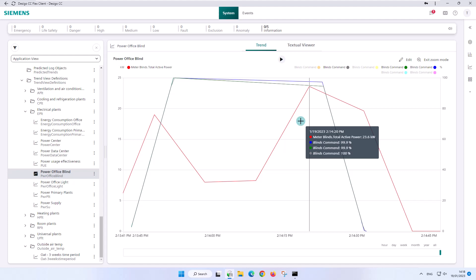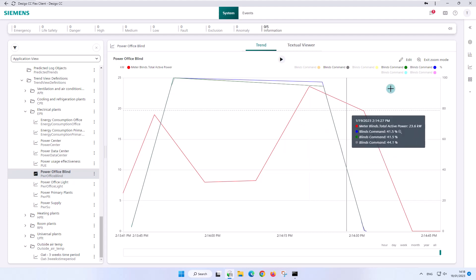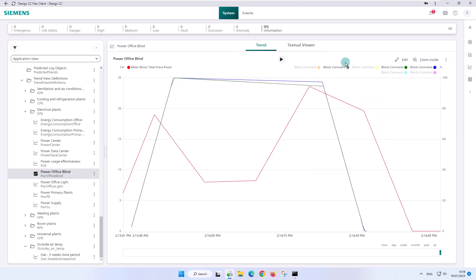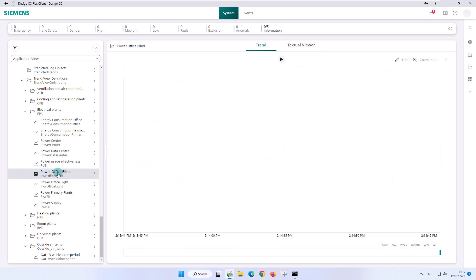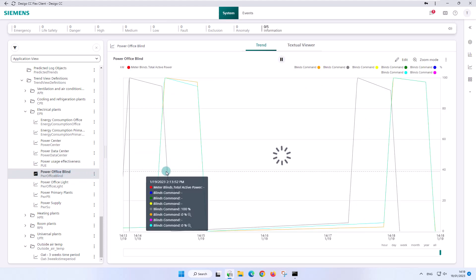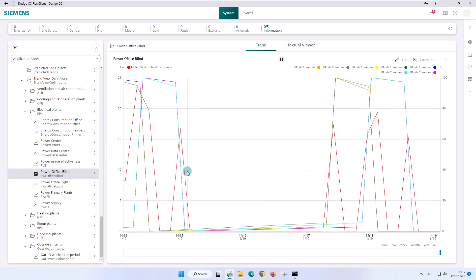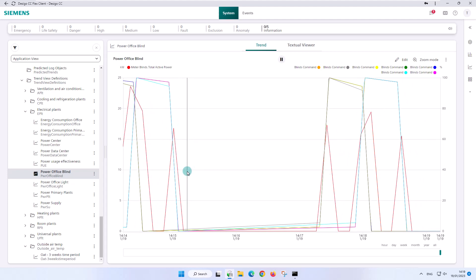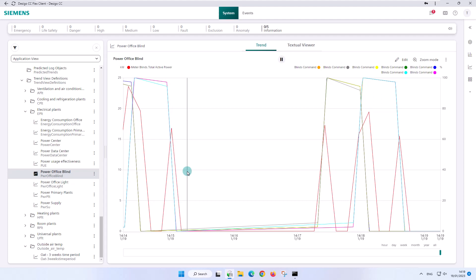Holding the cursor over the desired peak value will display the various values of the data points, as well as the date and time of occurrence. After the completed analysis, we exit the zoom mode and release the update. By reselecting the trend view definition, it can be seen that all the changes that have just been made are temporary. The data point values of this trend view can be displayed in a chart because they are of the same analog data point type.